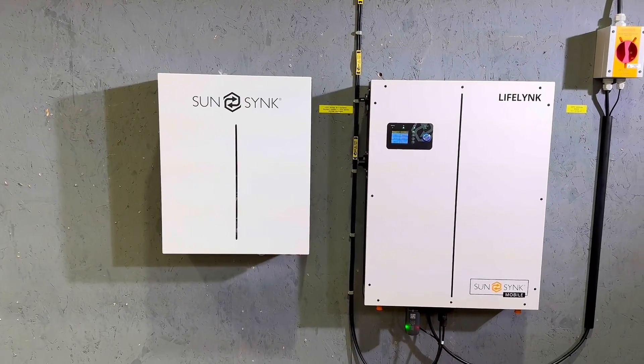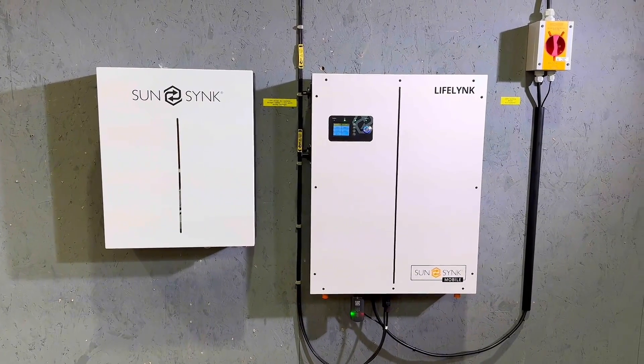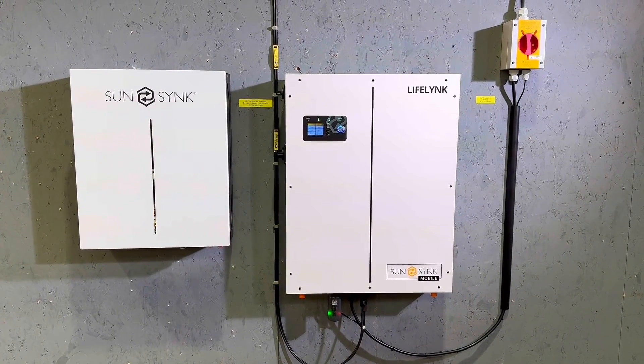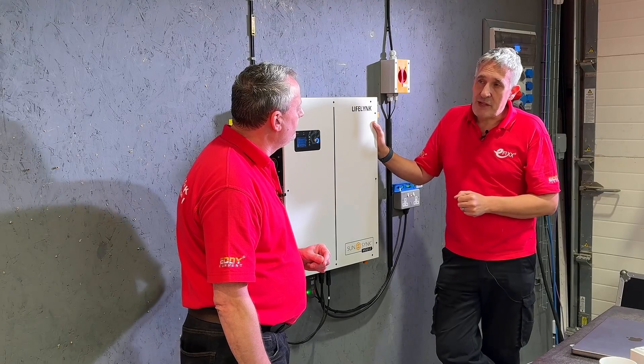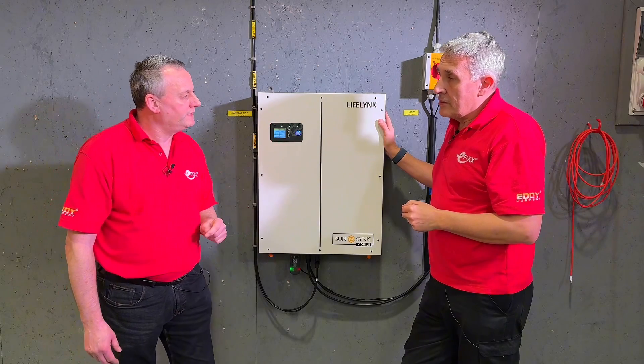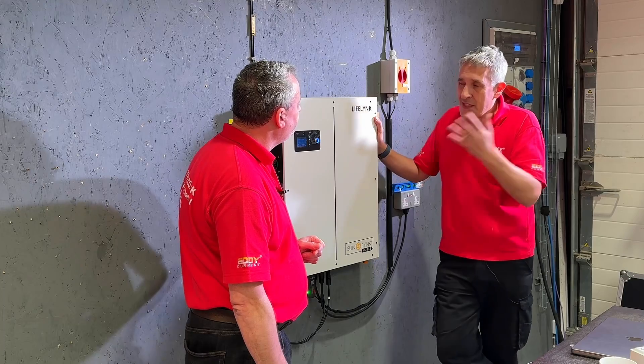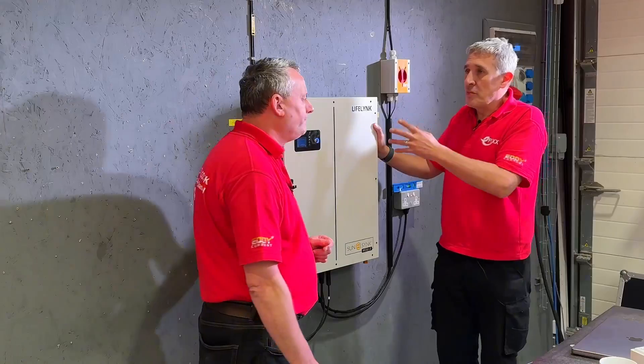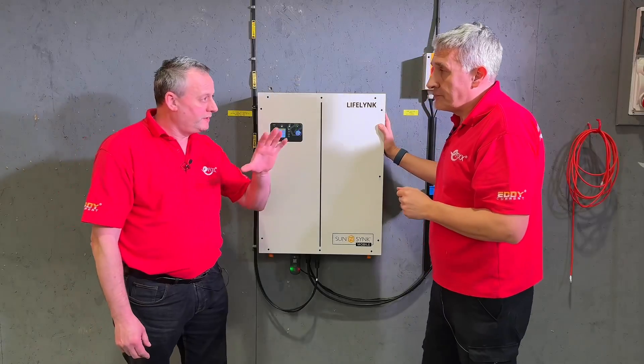Or if you couldn't add more solar because you're limited on roof space but wanted more battery capacity — to buy in some of that cheap variable tariff energy — you can add traditional Sun Synk batteries to this via the additional battery terminals and the BMS output at the bottom. So you can communicate with those batteries, adding about five kilowatts or slightly over to whatever battery is in the LifeLynk setup. And if you didn't have space, you could distribute these around a little bit like storage heaters, or put this in the garage with your batteries all in one location.